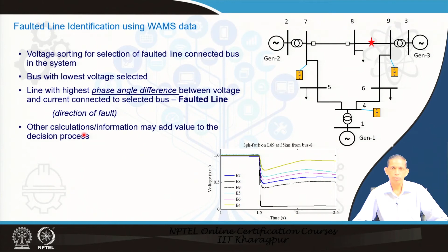So, what do you do? Sort the voltage to identify the faulted line, with the bus with the lowest voltage being selected, and the line with the highest phase angle, whichever lines are connected to that lowest voltage bus. The phase angle difference between voltage and the current connected to the bus indicates the faulted line, because the phase angle will be indicative of direction. So, the PMU data here can be useful for the decision process, which adds value to the protection scheme. Now, let us see an example of what is being done.